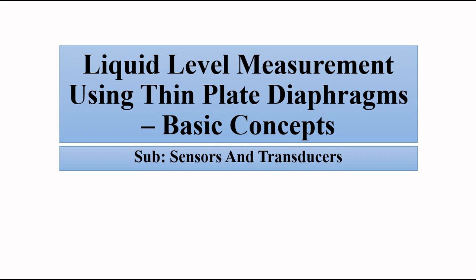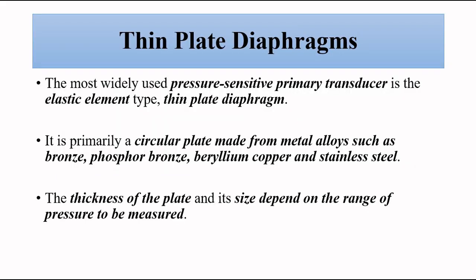So a quick recap. Thin plate diaphragms, like bellows and Bourdon tube, are primary mechanical transducers. What does that mean? Primary transducers give a non-electrical output, basically physical movement or displacement, angular or linear, rotation or linear displacement. It responds to the changing parameter with to and fro movement, linear movement, angular movement. So we have to use another transducer, called a secondary transducer, which converts that mechanical movement into electrical output, voltage or current.